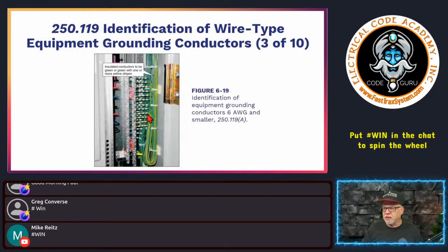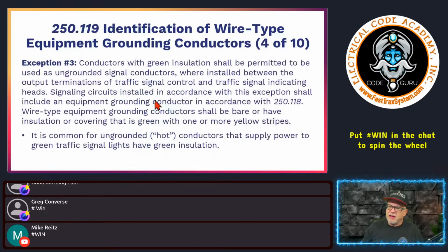Anyway, this is just showing you some green and yellow. All right, exception number 3. It says conductors with green insulation. And these are exceptions, by the way, for the green or the green with yellow on all equipment grounds that are insulated. It says conductors with green insulation shall be permitted to be used as ungrounded signal conductors where installed between the output termination of a traffic signal control and a traffic signal indicating head, okay, traffic lights, that type of thing. Signaling circuits installed in accordance with these exceptions shall include an equipment grounding conductor in accordance with 250.118, so that's our list, so we have to have an equipment grounding conductor by the list. And the wire type equipment grounding conductor shall be bare or have insulation that is green with one or more yellow stripes. So it can be bare or it has to be green with one or more yellow stripes.